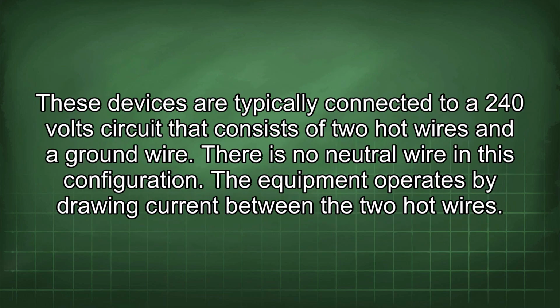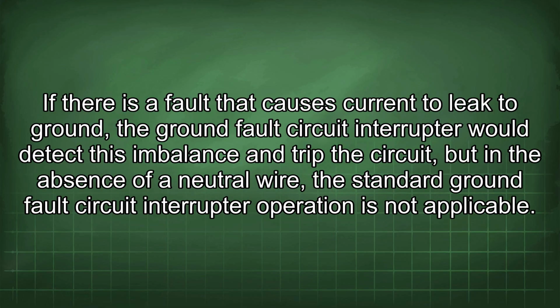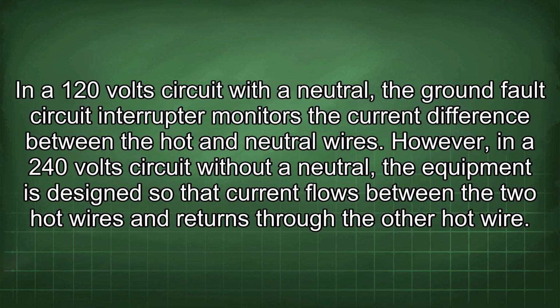These devices are typically connected to a 240-volt circuit that consists of two hot wires and a ground wire. There is no neutral wire in this configuration. The equipment operates by drawing current between the two hot wires. If there is a fault that causes current to leak to ground, the ground fault circuit interrupter would detect this imbalance and trip the circuit, but in the absence of a neutral wire, the standard ground fault circuit interrupter operation is not applicable.